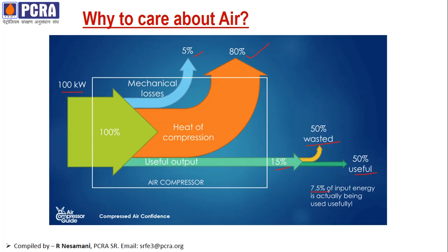See, if you see the compressor operation, if you give 100 kilowatt of power, the mechanical losses will be 5% and heat of compression will be 80%. So the useful output will be 15%, useful output in the form of pressurized air. In that also, industries waste in the form of leakages, artificial demand and misusing the compressed air. So almost 50% is lost in that also. So only the 50% remaining air is being used for process. So we can say that only 7.5% of the input energy is actually being used by the industries.